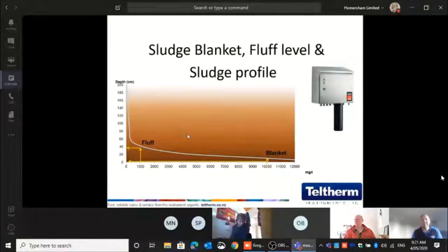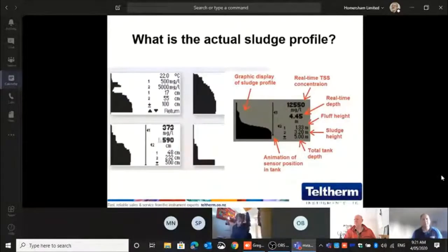This is what the unit basically outputs. You give it a value for the fluff level and a value for the blanket level. When the unit goes down, there are two outputs. One will be the fluff output. It will tell you where it finds 1000 milligrams per liter. And when it hits 1%, it will tell you exactly what the height is as well. Outputs number 3 and 4 are basically depth versus concentration, or height versus concentration. You can choose that. So basically you see the profile. That's basically how it looks.